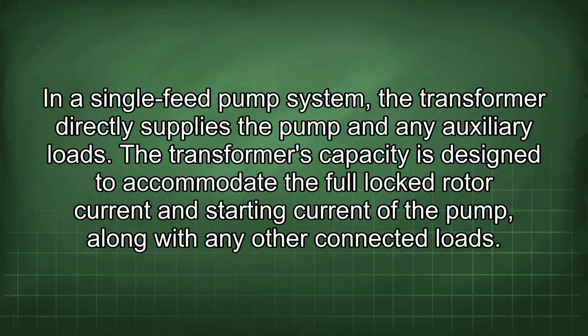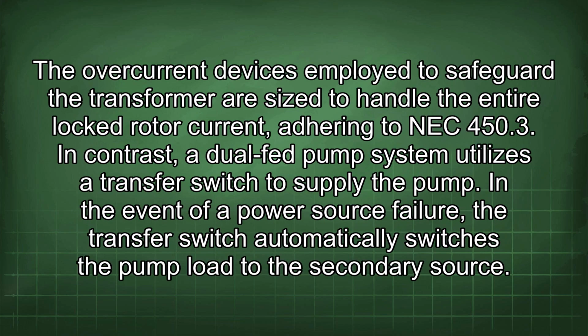In a single-feed pump system, the transformer directly supplies the pump and any auxiliary loads. The transformer's capacity is designed to accommodate the full locked rotor current and starting current of the pump, along with any other connected loads. The overcurrent devices employed to safeguard the transformer are sized to handle the entire locked rotor current, adhering to NEC 450.3.